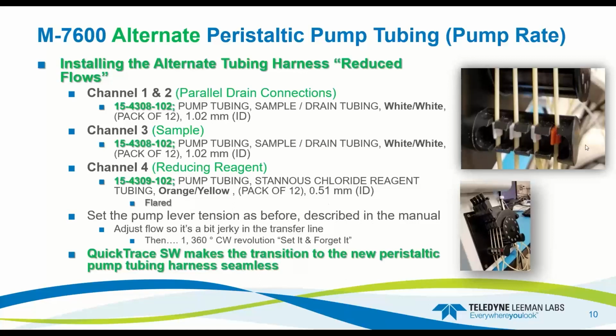And then the reducing agent, the stannous chloride, is 15-4309-102, and that is orange-yellow, 0.51 millimeters and 1.02 millimeters for this tubing. So setting the tension is exactly the same as what you would have done with the original tubing. It's also described in the manual.